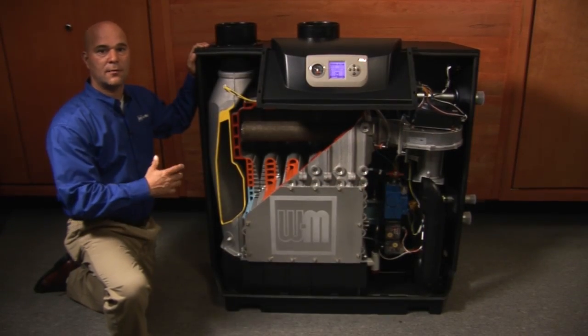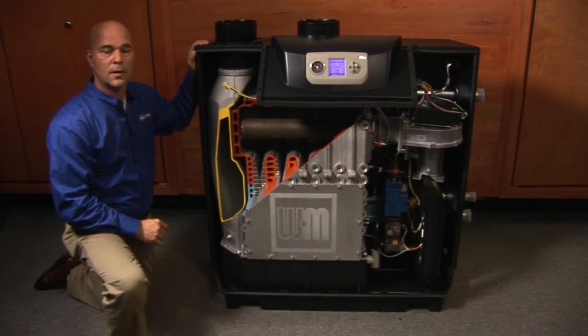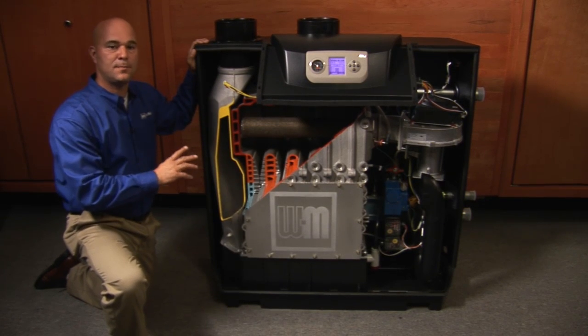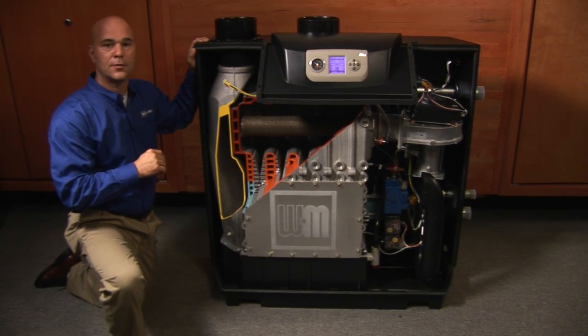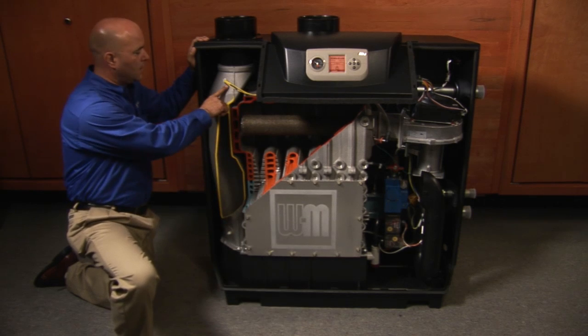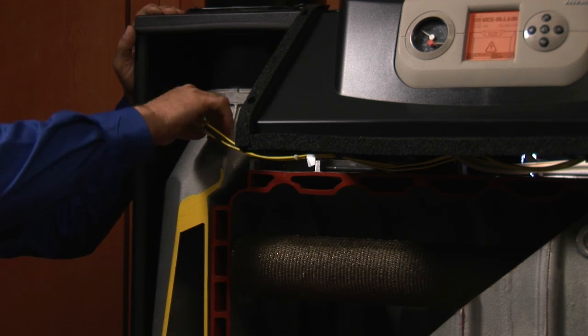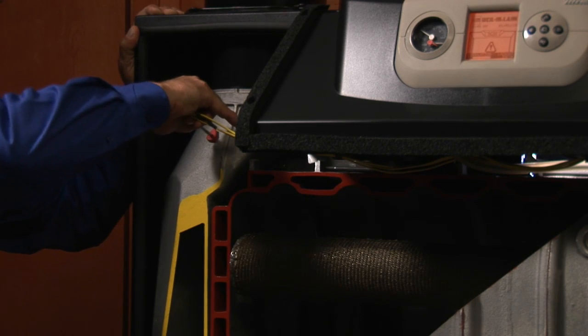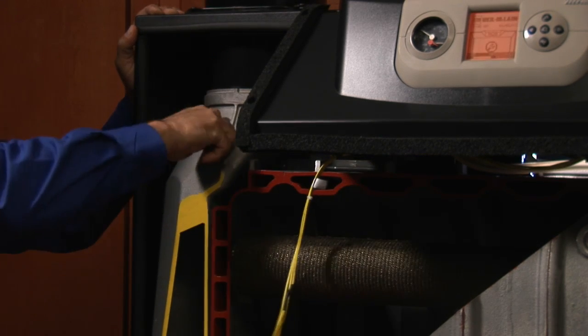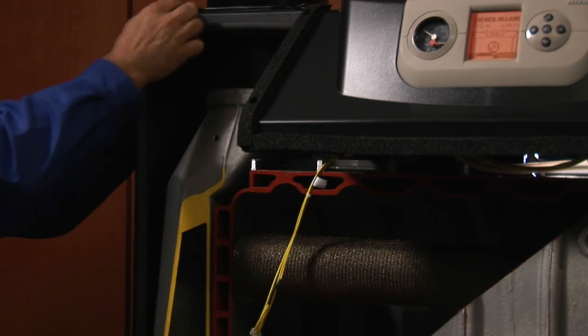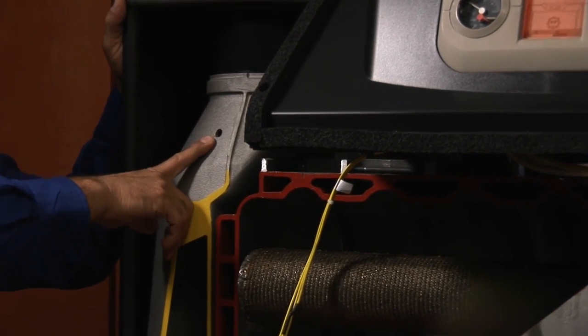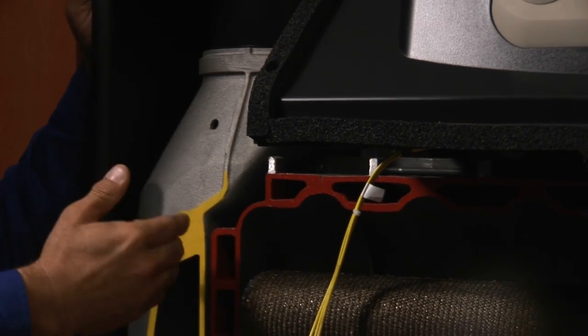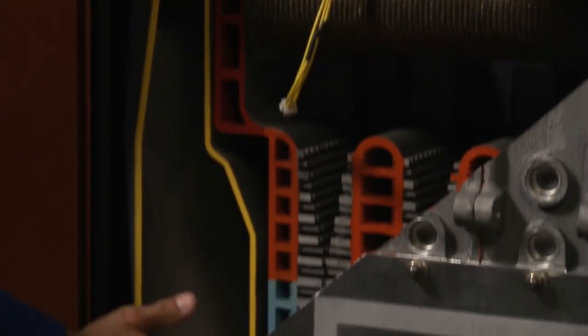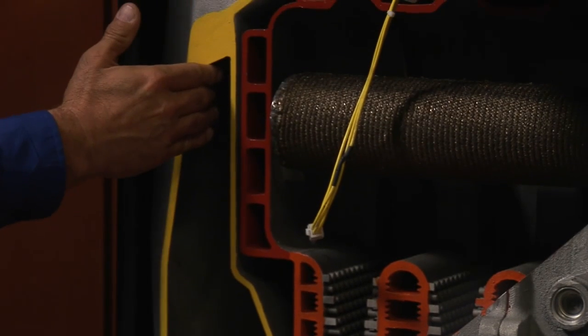Okay, now that we have the cover off the ultra commercial boiler, we're going to go through and just point out key spots on the boiler and go through the components on the boiler. This is the exhaust port. This sensor will be removed. You can pull this sensor out and then remove the rubber grommet. And if you're doing a combustion test, this is where you'll take your combustion test. This is the flue passageway up to the transition to the PVC.